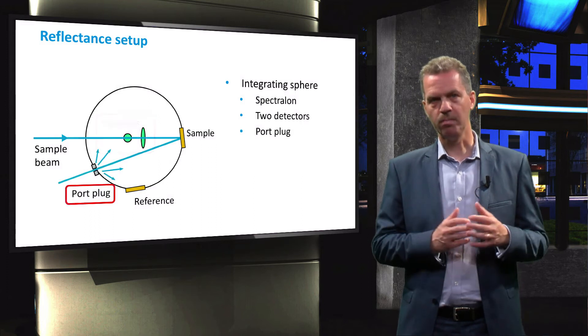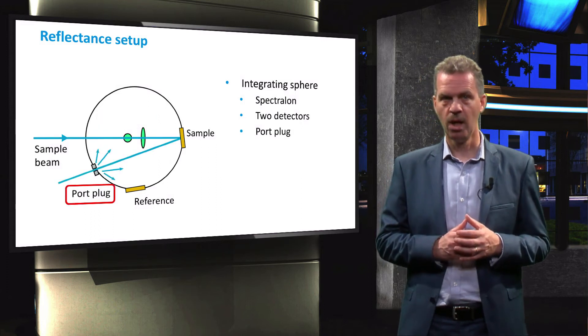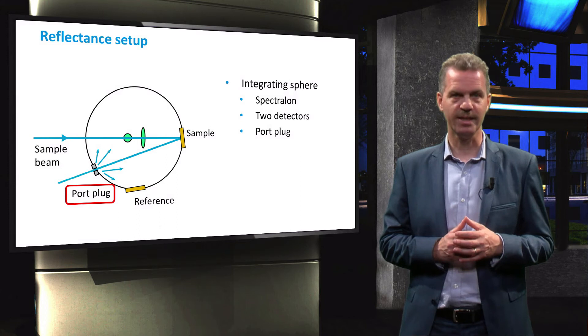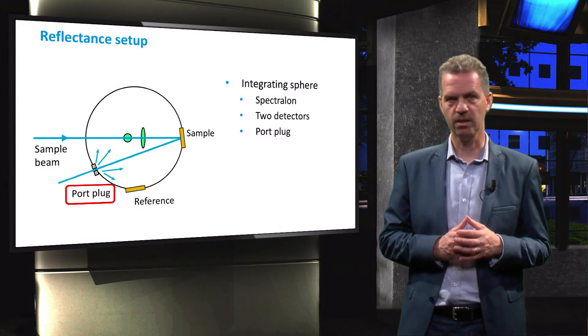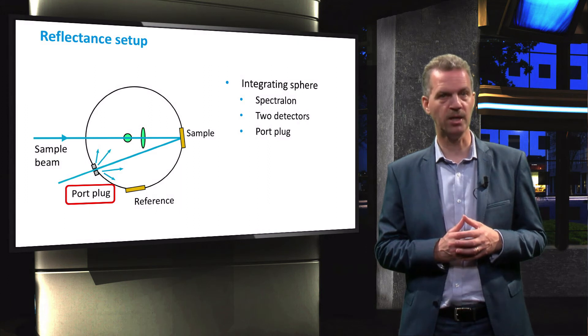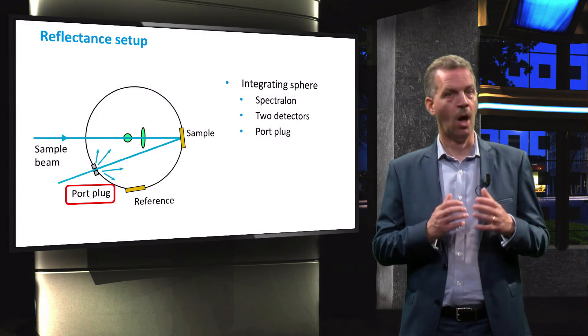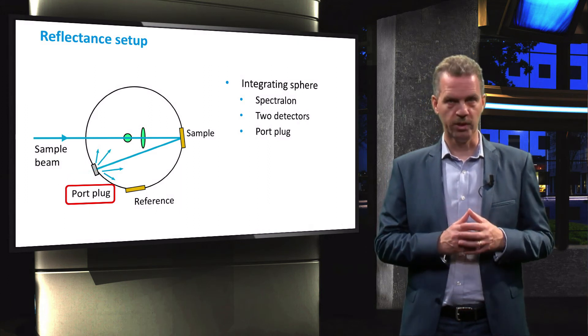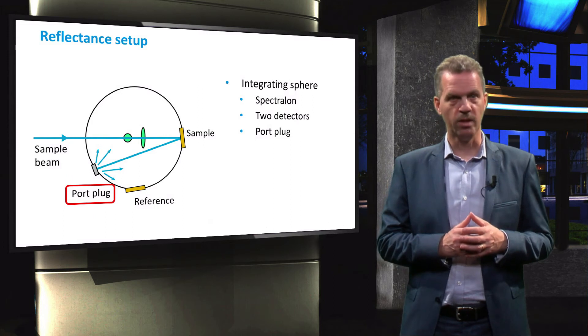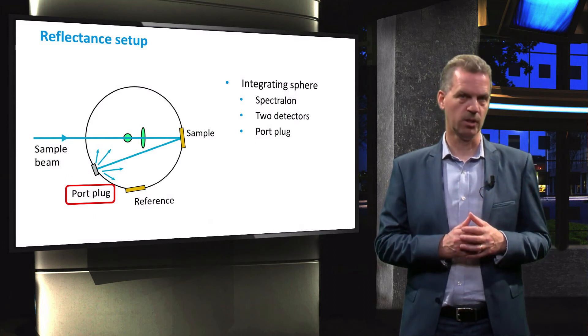When the sample beam is focused on the sample, the specular reflected light is directed towards an opening in the sphere, which can be used to remove specular reflection and measure only the diffuse reflection. When the port is closed with spectralon, the total reflection will be measured.